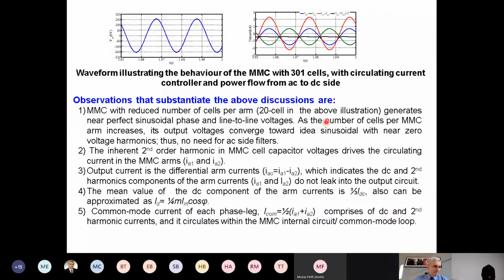So we can summarize as follows. The MMC with a reduced number of cells per arm, like for example 20 cells, as in this example, generates nearly perfect sinusoidal phase and line voltage. As the number of cells per MMC arm increases, its output voltage converges toward ideal sinusoidal, as you can see from here. So with nearly zero harmonics, in this case, there is no need at all for any kind of filter.